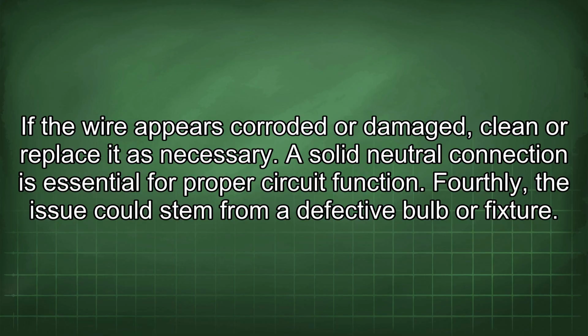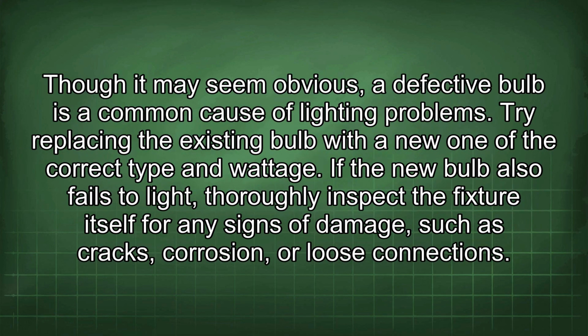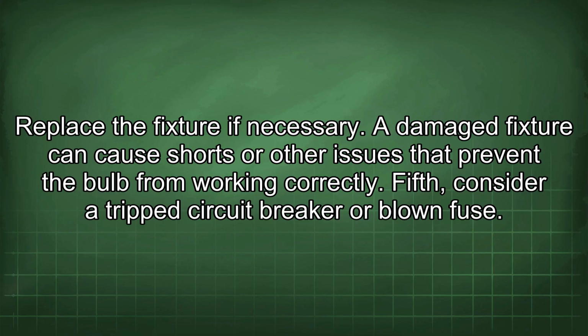Fourthly, the issue could stem from a defective bulb or fixture. Though it may seem obvious, a defective bulb is a common cause of lighting problems. Try replacing the existing bulb with a new one of the correct type and wattage. If the new bulb also fails to light, thoroughly inspect the fixture itself for any signs of damage, such as cracks, corrosion, or loose connections. Replace the fixture if necessary. A damaged fixture can cause shorts or other issues that prevent the bulb from working correctly.